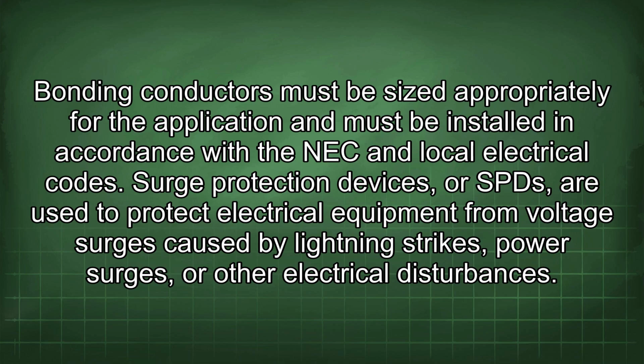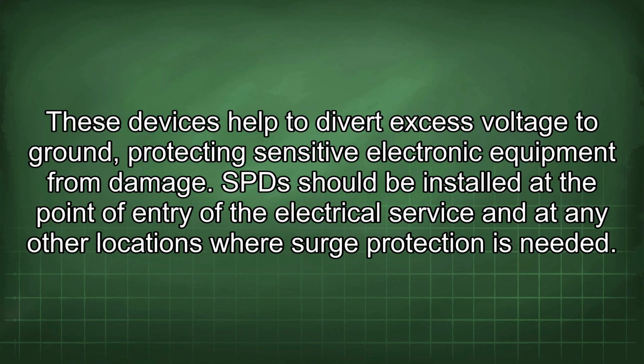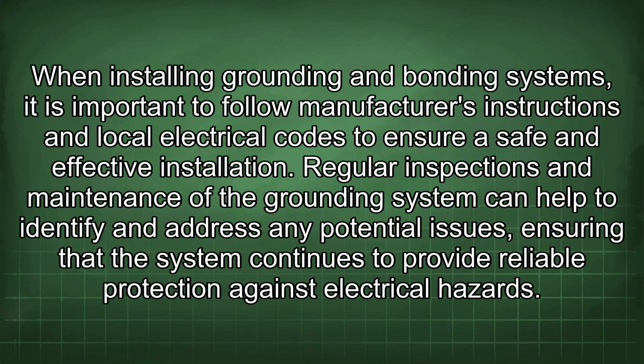electrical codes. Surge protection devices, or SPDs, are used to protect electrical equipment from voltage surges caused by lightning strikes, power surges, or other electrical disturbances. These devices help to divert excess voltage to ground, protecting sensitive electronic equipment from damage. SPDs should be installed at the point of entry of the electrical service and at any other locations where surge protection is needed. When installing grounding and bonding systems, it is important to follow manufacturers' instructions and local electrical codes to ensure safe and effective installation.